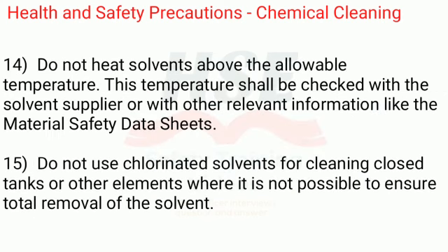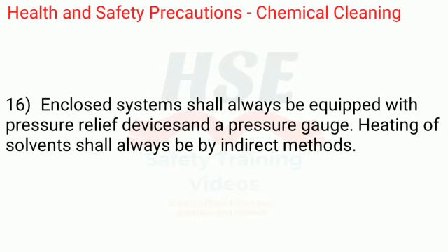14. Do not heat solvents above the allowable temperature. This temperature shall be checked with the solvent supplier or with other relevant information like the material safety data sheets. 15. Do not use chlorinated solvents for cleaning closed tanks or other elements where it is not possible to ensure total removal of the solvent. 16. Enclosed systems shall always be equipped with pressure relief devices and a pressure gauge. Heating of solvents shall always be by indirect methods.